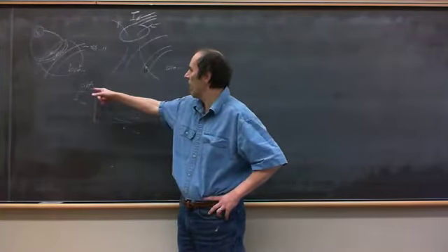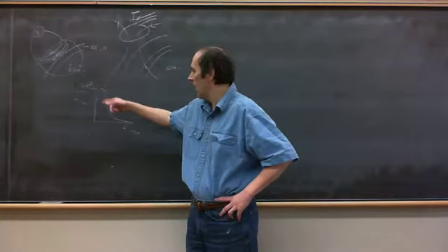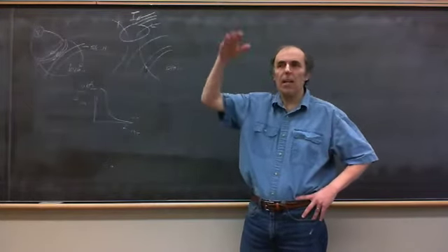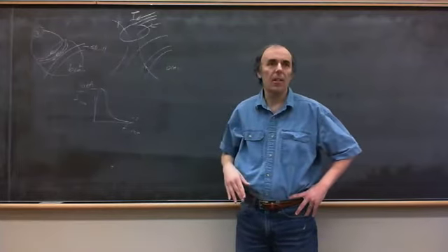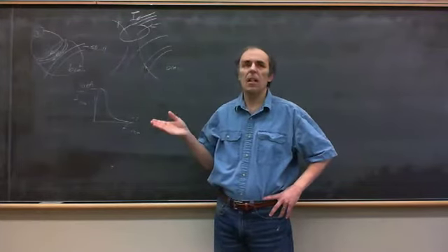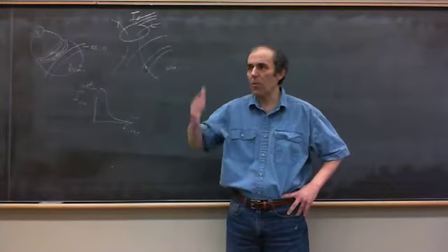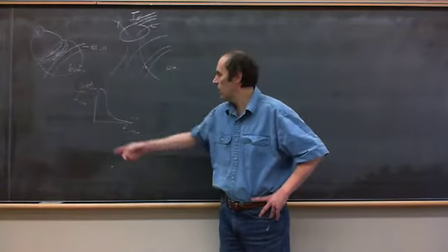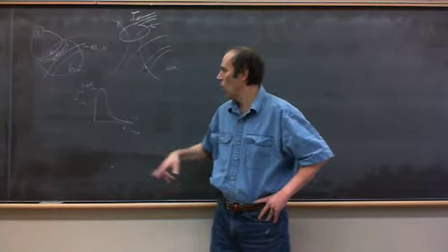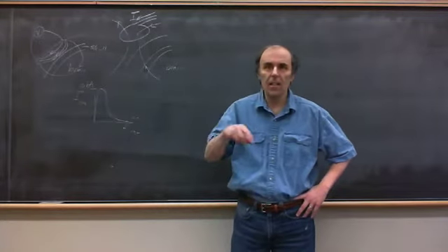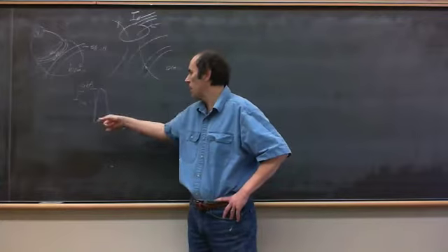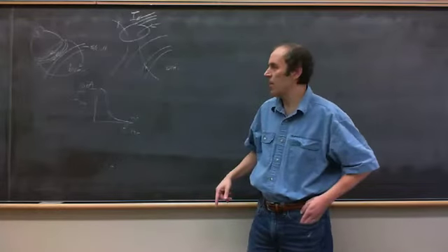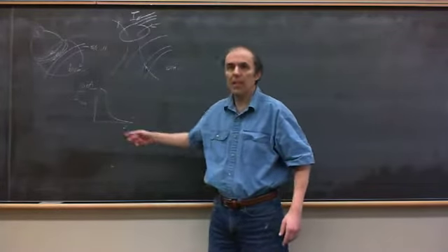And this induces magnetic fields on the order of about 2 Tesla. So your magnetic field rises by a couple Tesla in 1/10 of a millisecond. So you're getting about 2 times 10 to the 4th Tesla per second. That's your rate of change of magnetic field, which is a very big change. That's the reason this works. It works because you're dealing with stimuli that are on the order of the length constant of the nerve axon, but it happens all very quickly. And you can try to do this repetitively, say 60 times a second, but then you start worrying about the coil heating up and other effects.